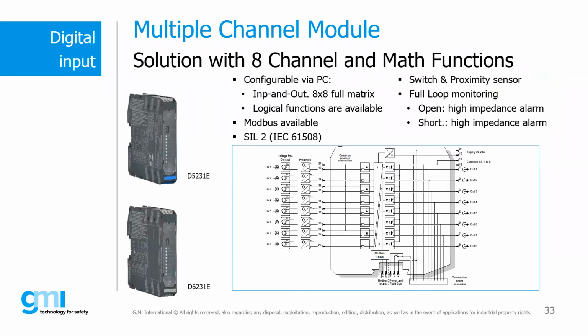We also do have a solution for 8 channels with multiple channels. And as for the 4 analog input modules, there are logic functions inside. So 8 inputs can be independent of each other, and the first output corresponds to the first input and so on. Otherwise, you can select specific functionalities and have a sort of matrix functionality. This is also available with the Modbus interface, and of course there is full loop monitoring for open and short circuits.